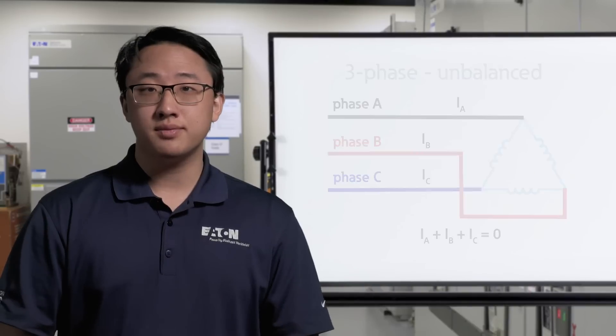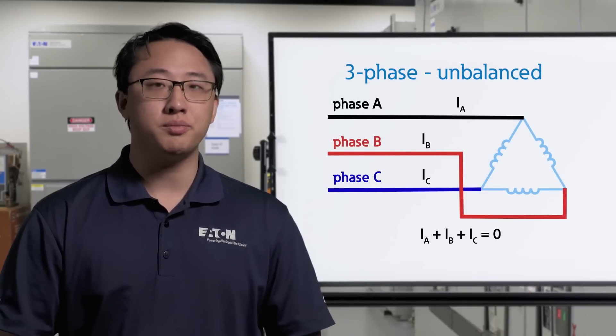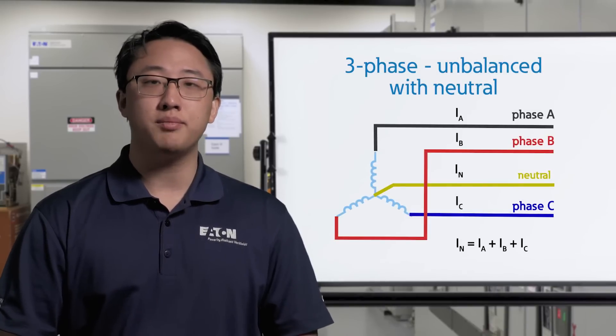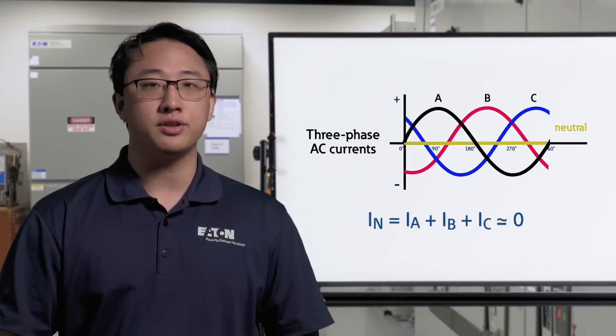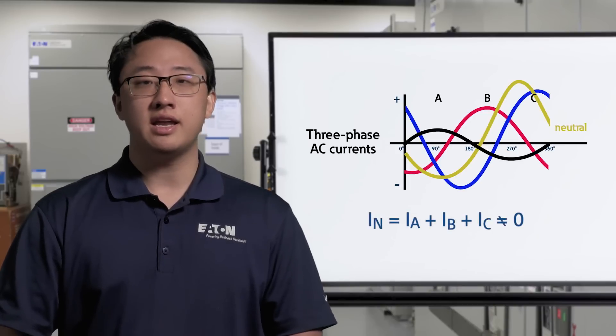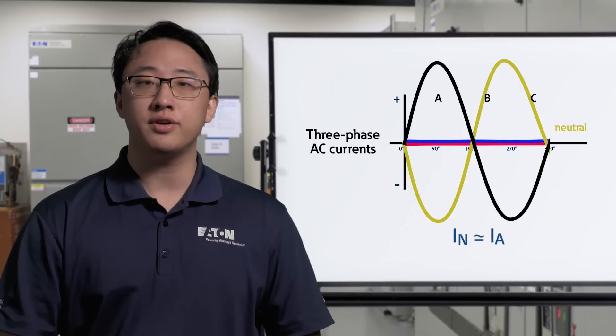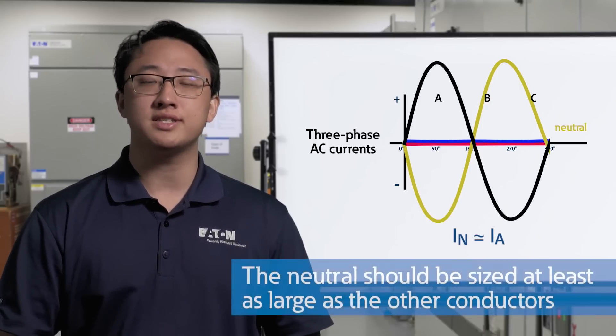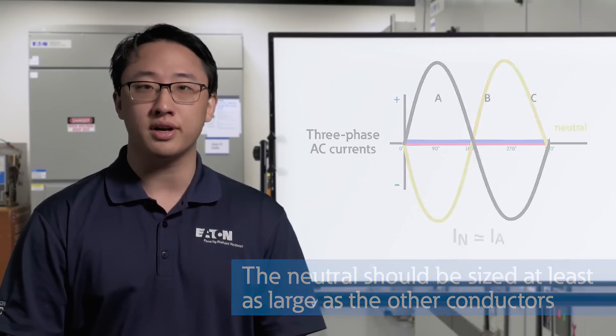Now, a three-phase system without a neutral could also have unbalanced currents, but they would still have to add up to zero or power would be restricted. Having a neutral allows for full power operation with unbalanced currents on each individual phase. A mostly balanced system won't carry too much current on the neutral, but poorly balanced systems can have significant amounts. In an extreme case, a single phase load on a three-phase system would have all of its current on one phase and returning on the neutral. This is why the neutral wire must be sized at least as large as the other conductors, oftentimes even larger today to account for extra harmonic content.